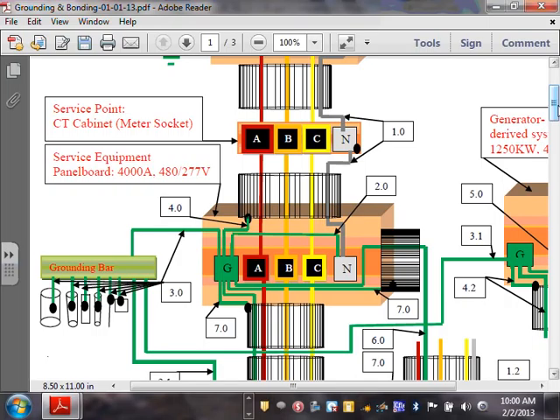Now we bonded the neutral right in here. Okay, everybody knows that. And then you have your ground bar here. The code says if you have a service in any building, you have to have at least 1 grounding electrode system. What's a grounding electrode system? A metallic object in direct contact with Mother Earth. So the code says if you have any system, grounded or ungrounded, you have to provide a grounding electrode system or systems, so you can bond the frame of your box, including the neutral in this case, to the grounding electrode systems, right?